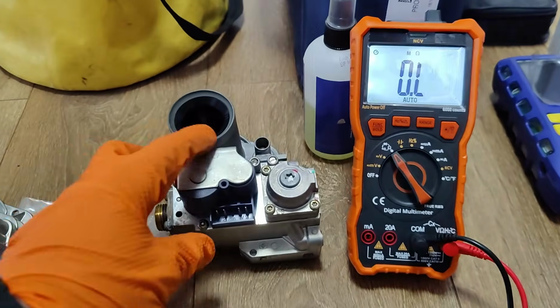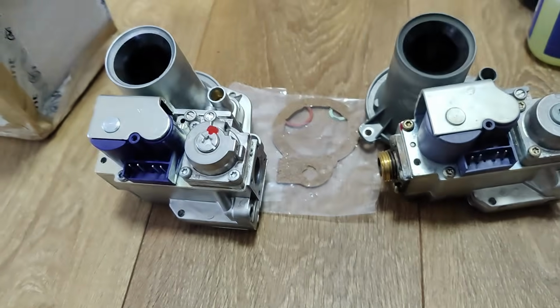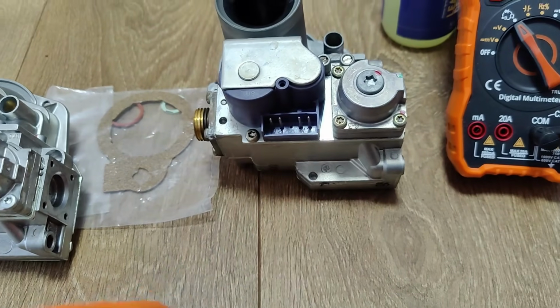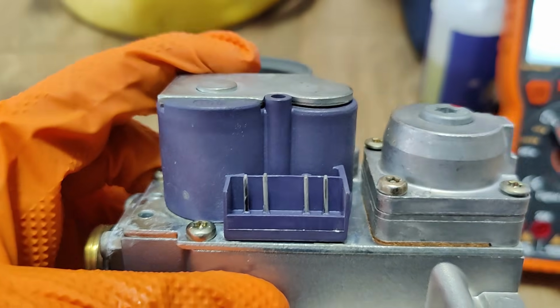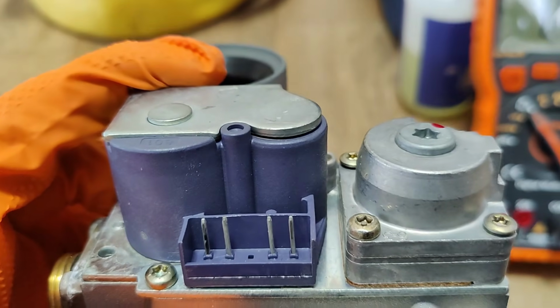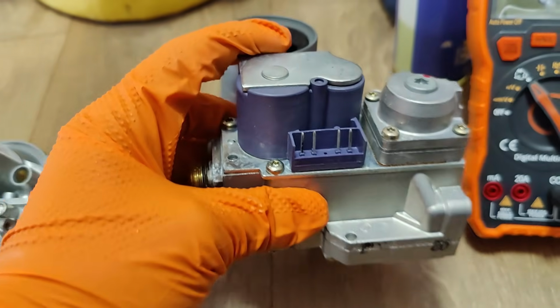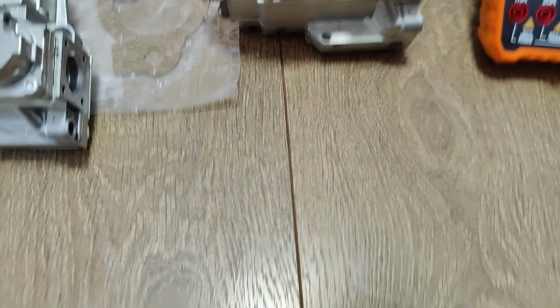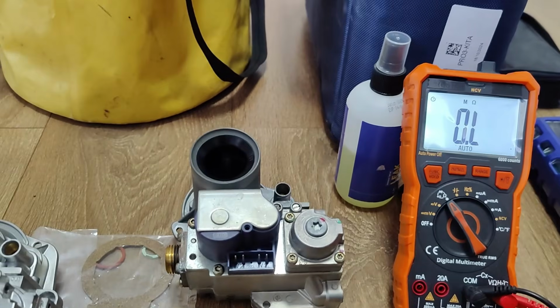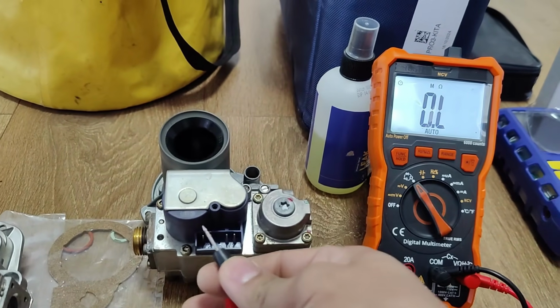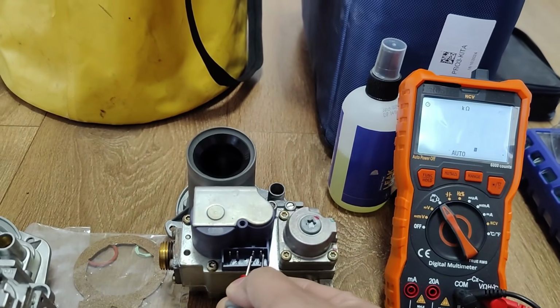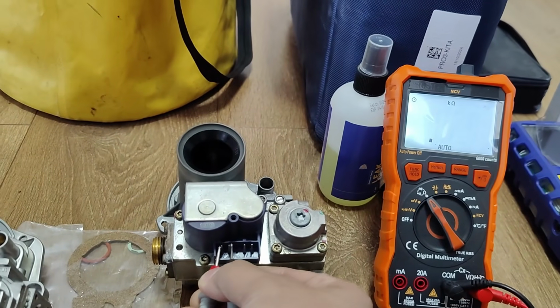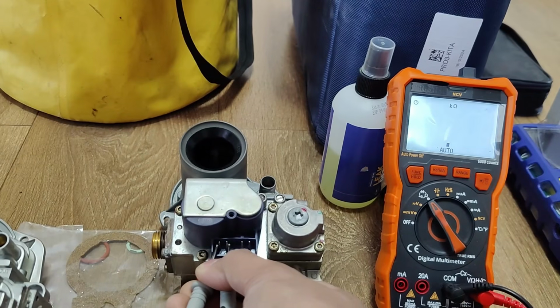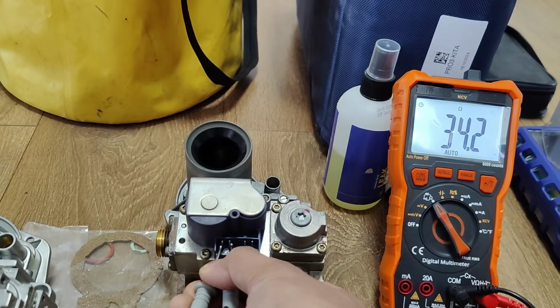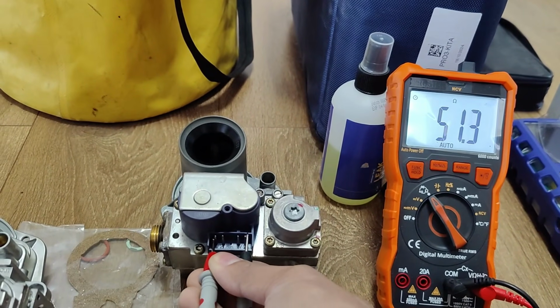Okay, so I have removed the old gas valve that I'm suspecting to be sticking. I have a brand new gas valve here next to it. So I'm just going to quickly check some resistance readings on these pins. As you can see, we have 4 pins here. The 2 pins on the right are for the smaller solenoid, and the 2 pins on the left are for the larger solenoid. So let's see what readings we're going to get out of that. Let's see if we can do it with one hand. Multimeter set to ohms reading, and let's see if this can be achieved. Okay, so separate coil, 17.3 ohms on the smaller one. If we can make good enough contact, 34 ohms on the larger one, and combined about 51 ohms.